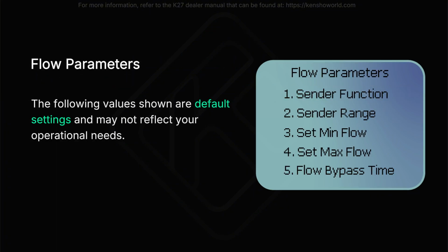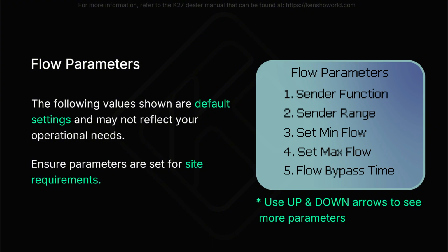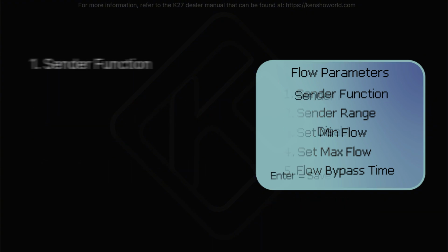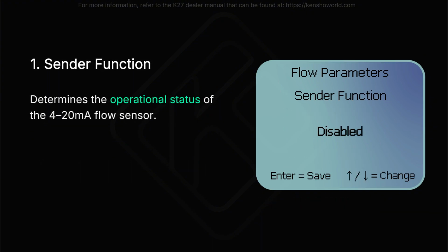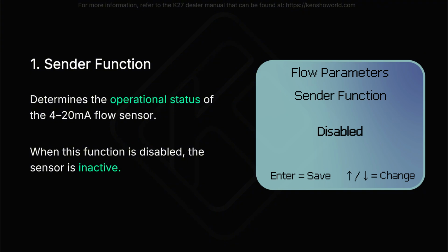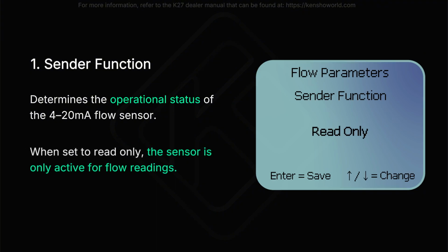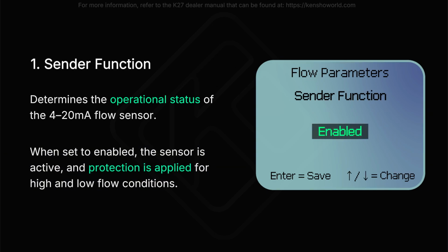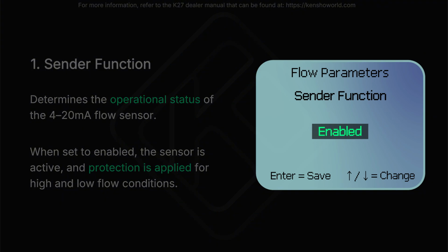The following values shown are default settings and may not reflect your operational needs. Please ensure that parameters are set according to site requirements. The sender function determines the operational status of the 4 to 20 mA flow sensor. When this function is disabled, the sensor is inactive. When set to read only, the sensor is active for flow readings only, without alarm protection. When set to enabled, the sensor is active, and protection is applied for high and low flow conditions.